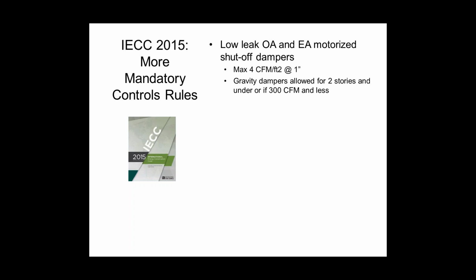Typically, rooftop manufacturers, air handling manufacturers, or damper manufacturers know what you mean if you tell them you need a low-leak damper. But if you want to be more detailed, you can specify a maximum of 4 CFM of leakage per square foot tested at 1 inch of pressure. You can use gravity dampers instead of motorized ones, as the code says, but only for small buildings that are 2 stories and less than 300 CFM. So for most systems, you're going to have motorized dampers. That ensures a tight shutoff and hence less leakage.